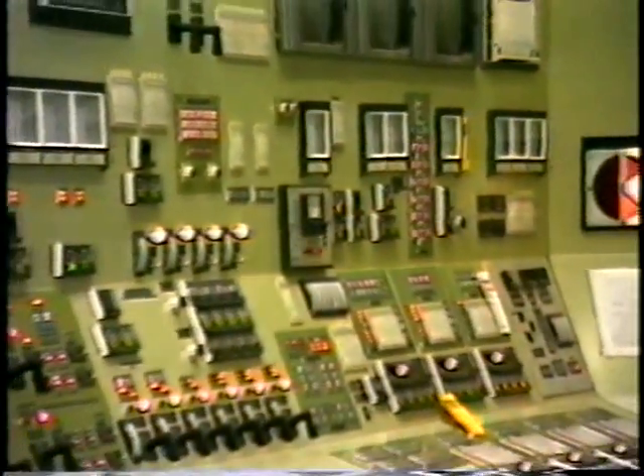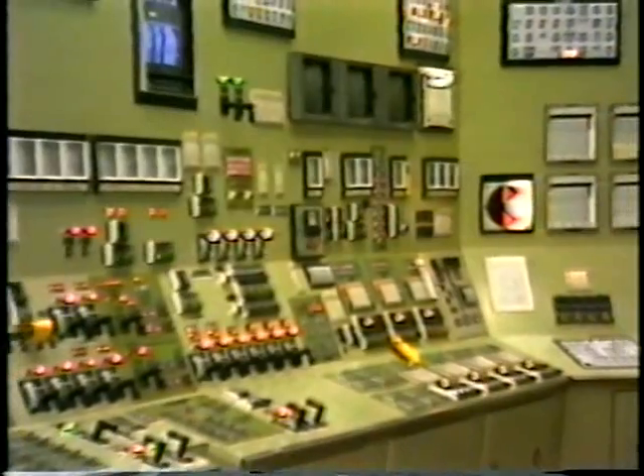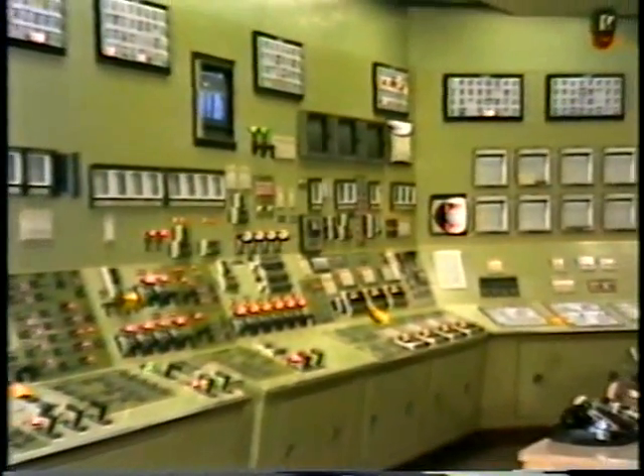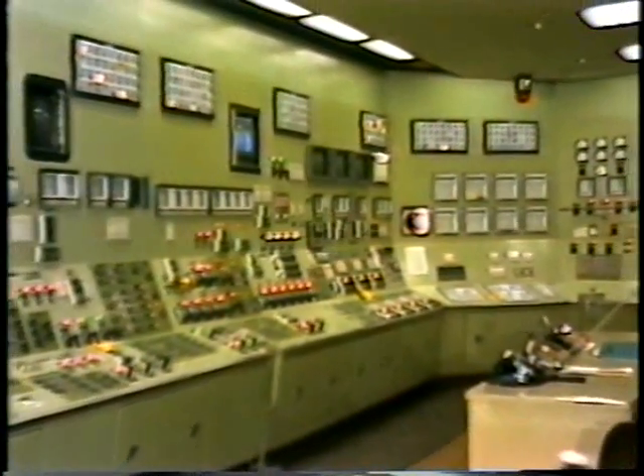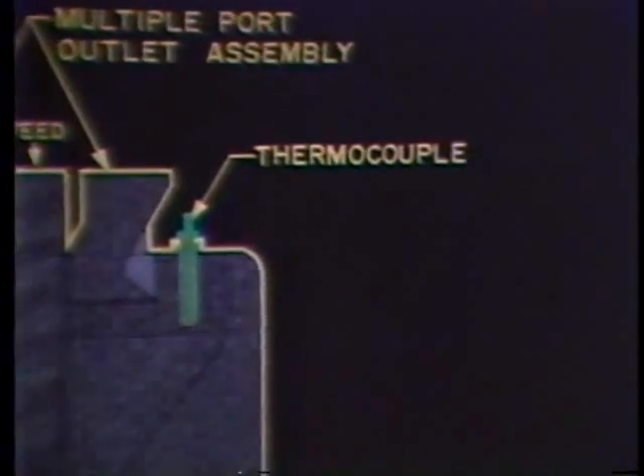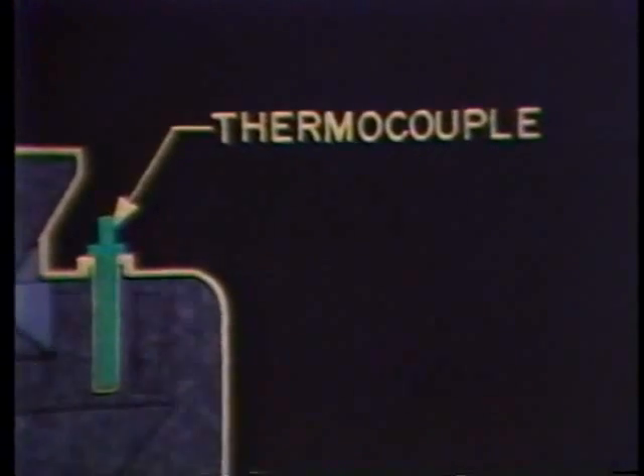Heretofore, detection systems have provided little or no warning time and have allowed fires and explosions to develop before corrective action could be taken. One method, that of using temperature sensing devices, such as thermocouples, which may be a part of the existing control system, has proven inadequate as a warning device. Several factors contribute to the ineffectiveness of the thermocouples. First, the necessary shielding that protects the thermocouple from the erosive mill atmosphere also reduces response time.